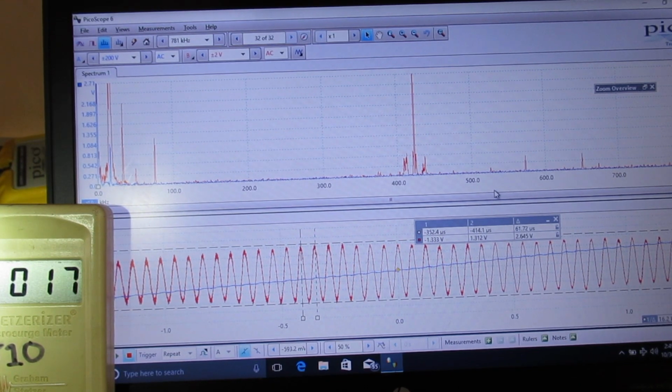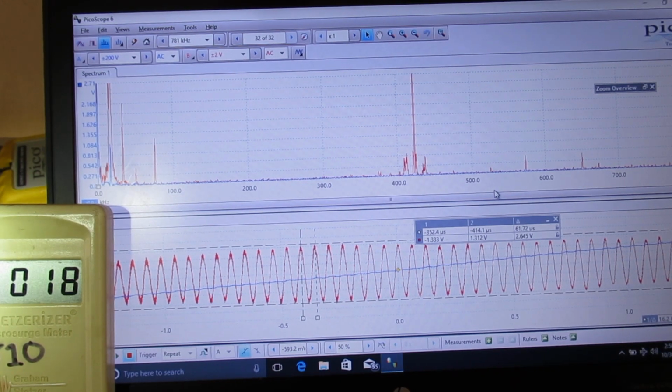So this is just the dirty electricity that's coming in on the utility feed lateral, and it's caused by dirty electricity devices next door. So this is what we actually have as an ambient, but we were up there at 3,480, and that was caused by the solar inverter.